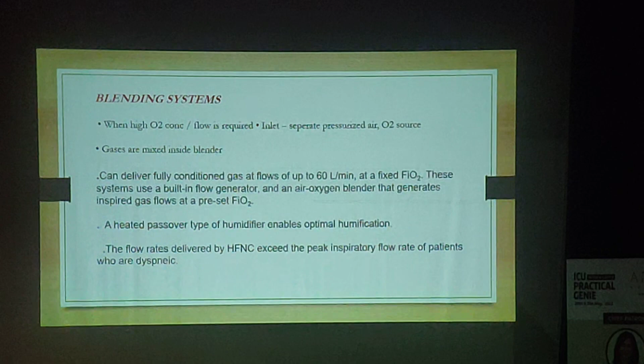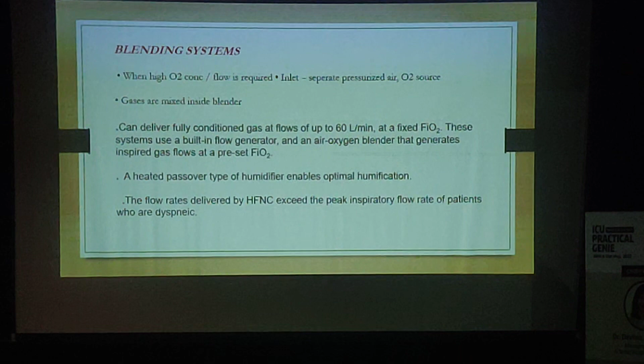And there is a separate pressurizing mixture or a device where the oxygen comes at a high flow. There is a pressurized chamber which mixes the oxygen and the air. The blending occurs, and these blended gases are then given to the patient. It can deliver fully conditioned gases with the inbuilt humidifiers that they have at 60 liters per minute at fixed FiO2s.